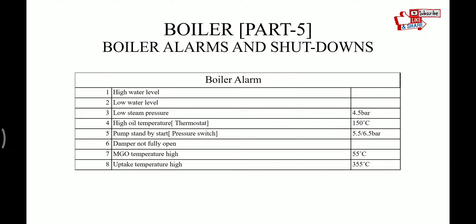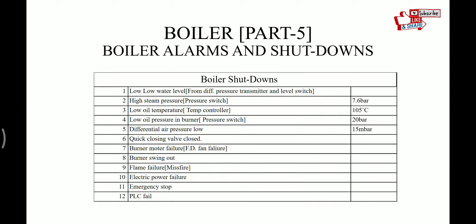Now boiler shutdowns. Low-low water level comes from two different sources: the differential pressure transmitter and the level switch. Then we have high steam pressure from the pressure switch, low oil temperature from the temperature controller, and low oil pressure in burner from the pressure switch.